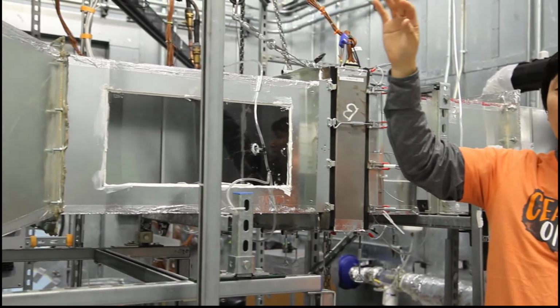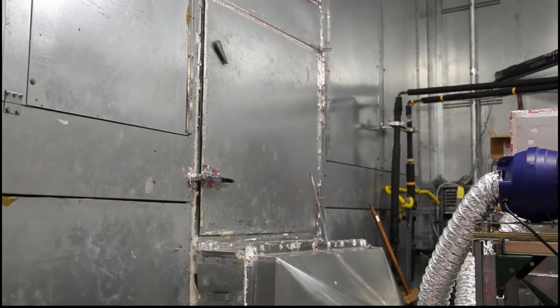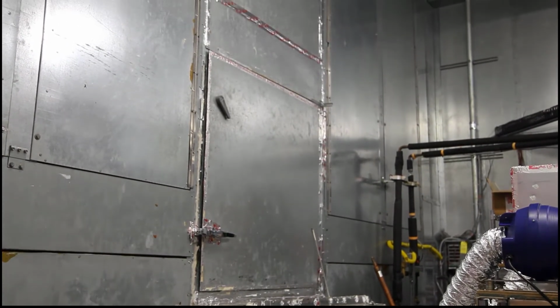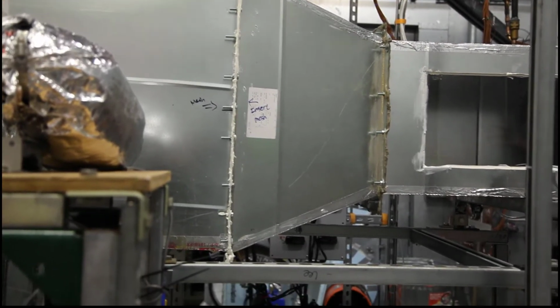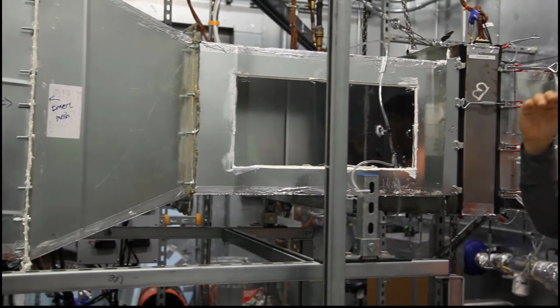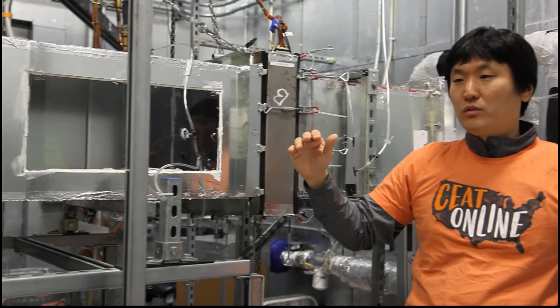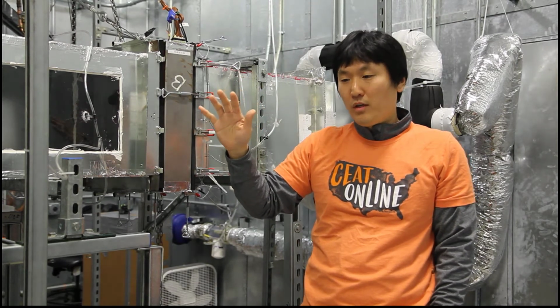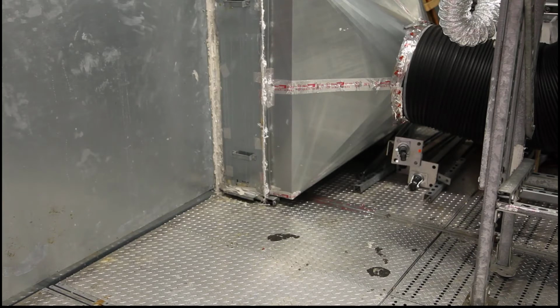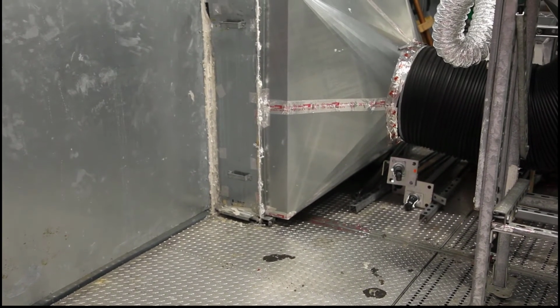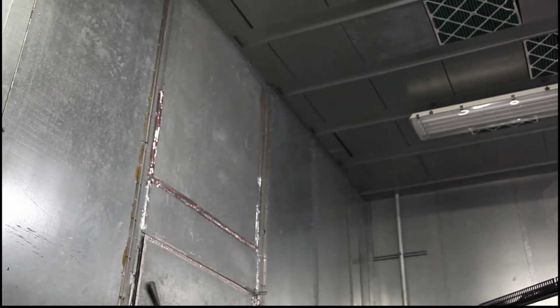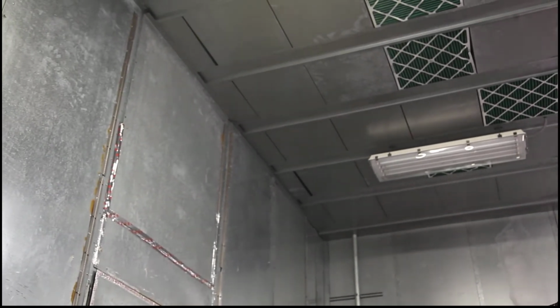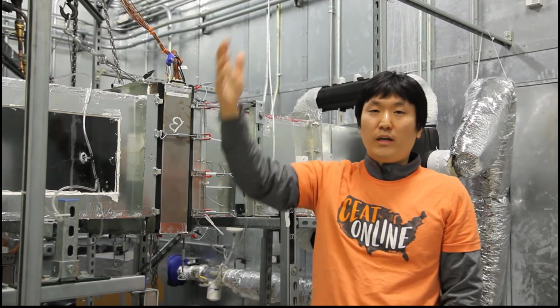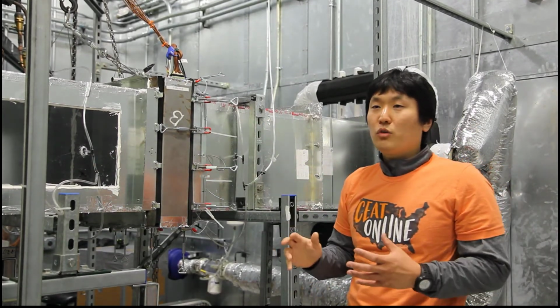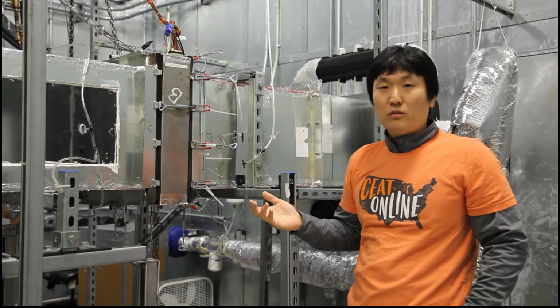the airflow going up and divided into 2 streams, and then going to the cooling coil, and then it's cooled down, and then we have separate heaters. So it's going up, the temperature can be controlled, and then we also have a humidifier, so the humidity is also controlled. So the temperature and humidity controlled airflow goes down and then comes up from the floor, and then it can generate uniform airflow, and then it's going up to the upper ceiling plenum, and then the airflow is circulating, keep going on. This is the unique feature of this psychrometric chamber, and this is the ductwork.